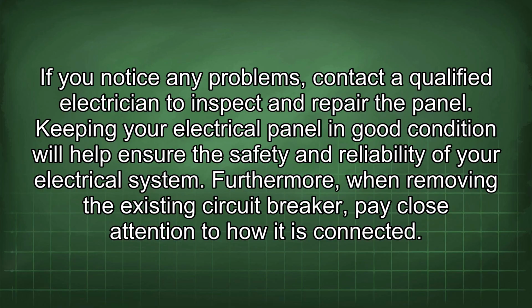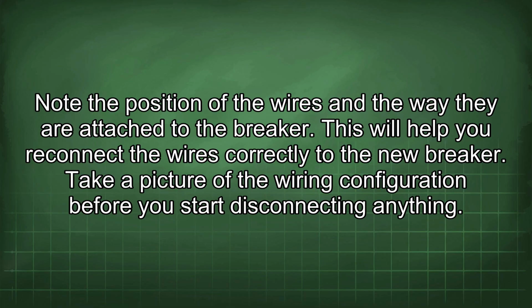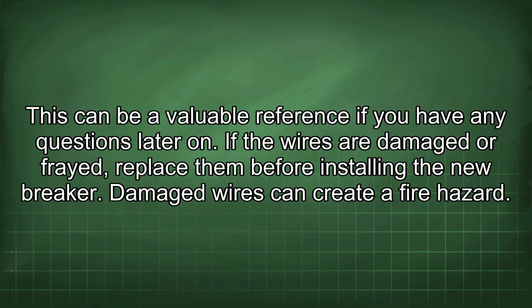Furthermore, when removing the existing circuit breaker, pay close attention to how it is connected. Note the position of the wires and the way they are attached to the breaker. This will help you reconnect the wires correctly to the new breaker. Take a picture of the wiring configuration before you start disconnecting anything. This can be a valuable reference if you have any questions later on.